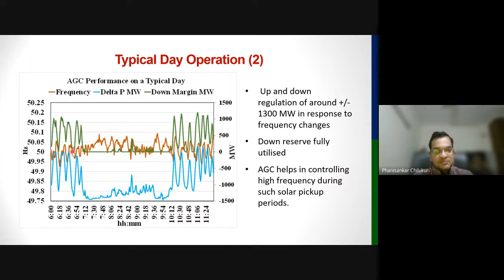And you can see that during high solar periods, AGC gave here 1500 down instruction continuously. This is one signal to the RRAS dispatch, manual RRAS dispatch, that okay, there is a 1500 megawatt offset. So RRAS, if you punch 1500, this secondary frequency control will be relieved, and it can do up and down cycling again. So like that, it helps in saving coal also in this way.